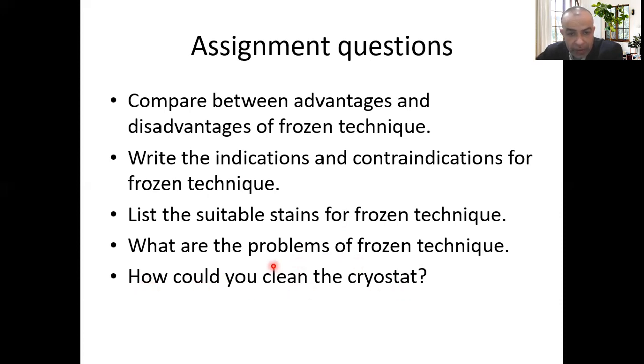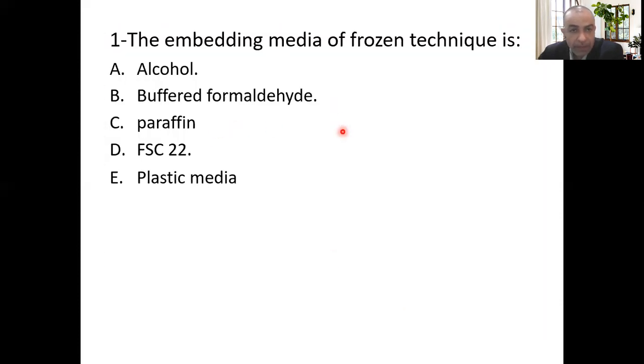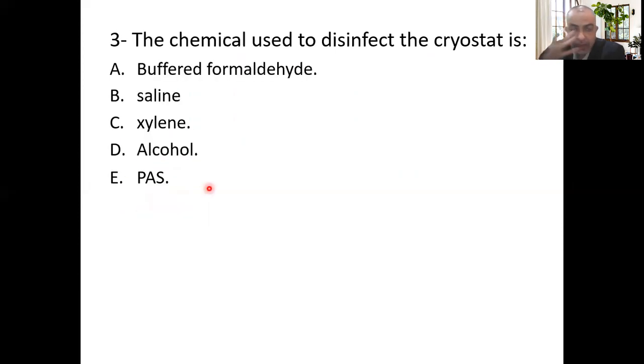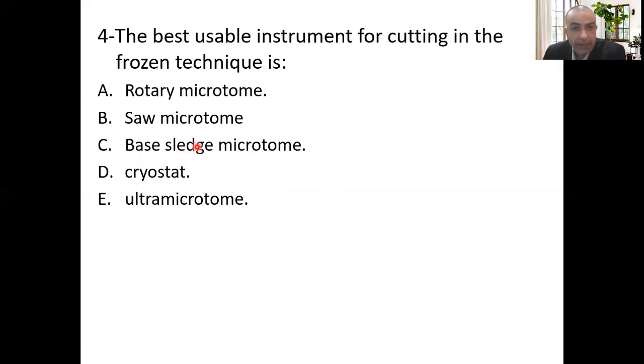How do you clean the cryostat? Seven steps — don't forget. MCQ: The embedding medium of the frozen technique is FSC 22. The adjusted temperature most suitable for most body tissues is minus 13 to minus 20. The chemical used to disinfect the cryostat is alcohol — we use hypochlorite, 70% alcohol, and 100% absolute alcohol. The best instrument for carrying out the frozen technique is the cryostat.